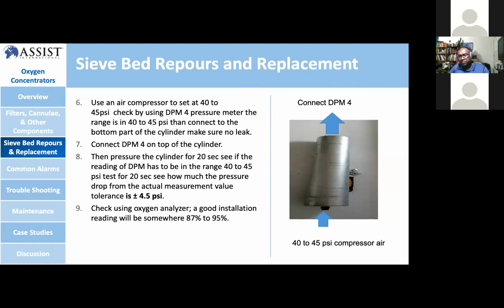So at the bottom part, you give a pressure of 40 to 45 PSI, and you connect your DPM4 on the top of the sieve tank. Then you pressurize the cylinder for 20 seconds and see if the DPM reading stays inside the range of 40 to 45. Test for 20 seconds and see if there's any leakage, within the tolerance of plus or minus 4.5 PSI. After that, check using an oxygen analyzer. Is the reading somewhere between 87 and 95? You can do that by installing it to your oxygen concentrator as well.